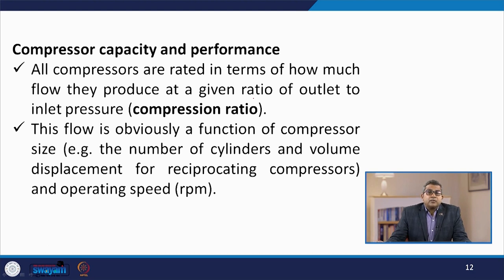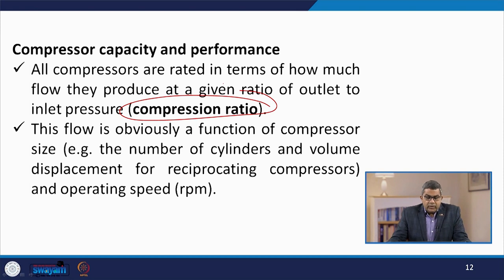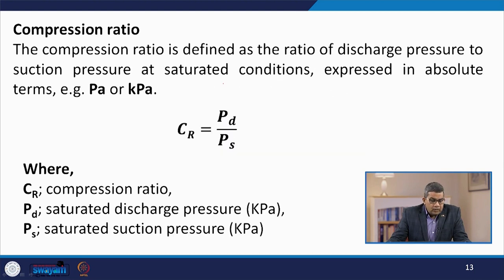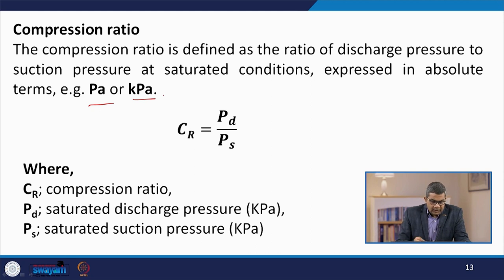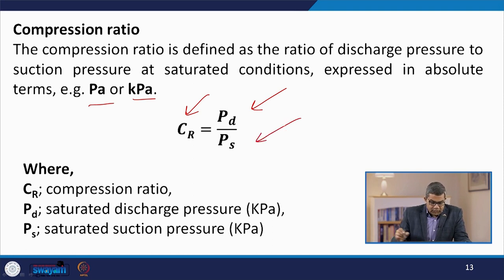Another prominent concept is compressor capacity and performance. All compressors are rated by the flow they produce at a given ratio of outlet to inlet pressure — the compression ratio. This flow is a function of compressor size (number of cylinders and volume displacement for reciprocating compressors) and operating speed in rpm. The compression ratio is defined as the ratio of discharge pressure to suction pressure at saturated conditions, expressed in absolute terms such as kPa: CR = P_D (kPa) / P_S (kPa).